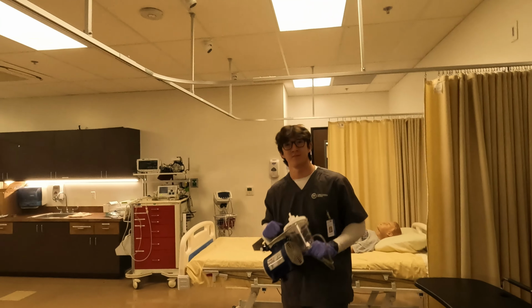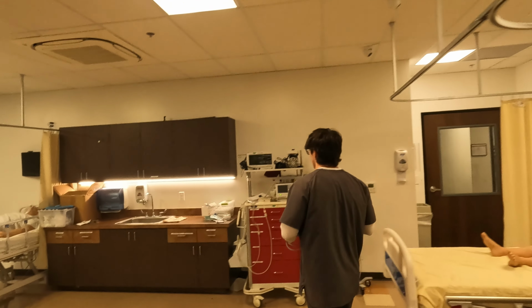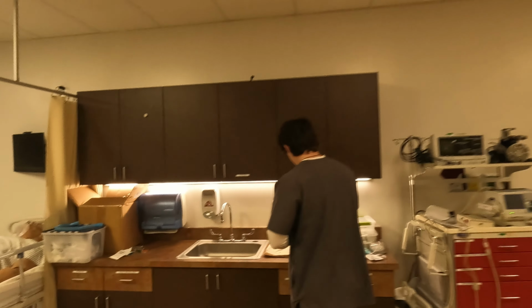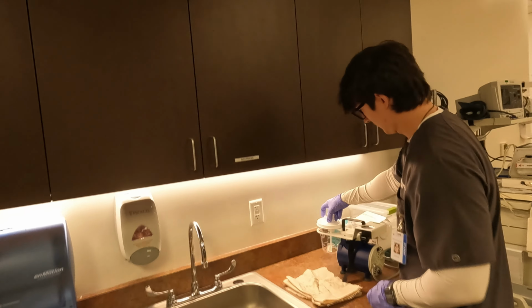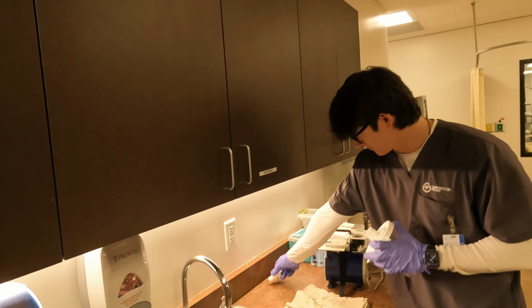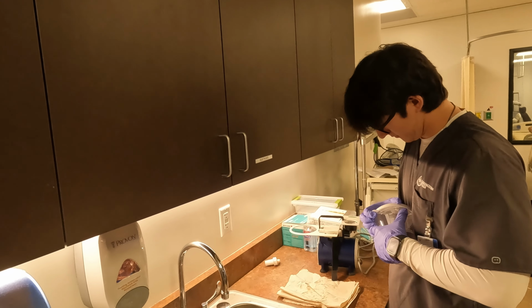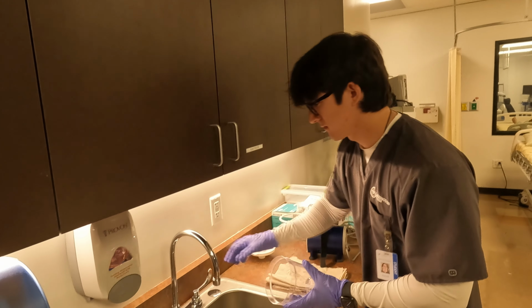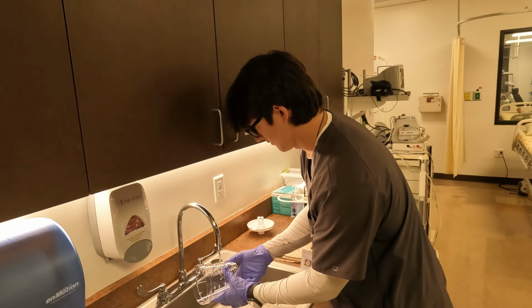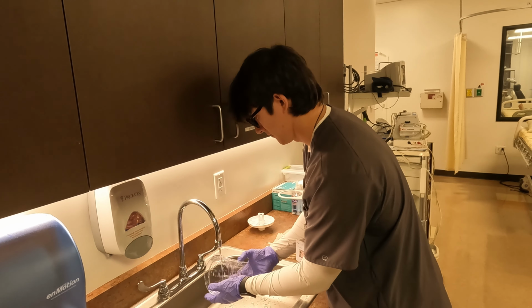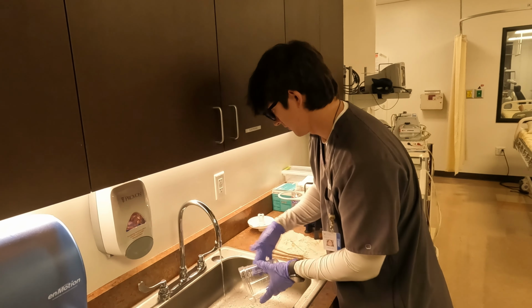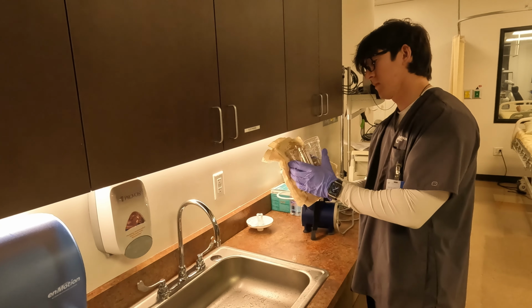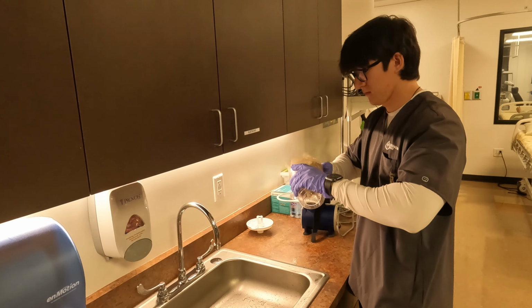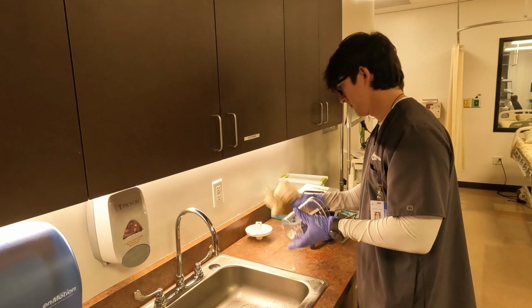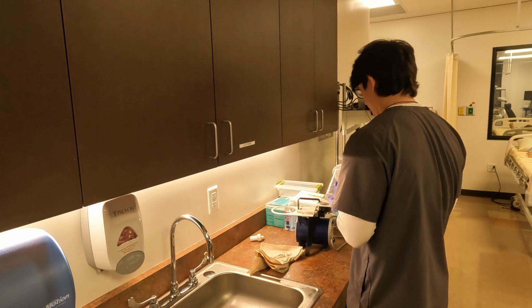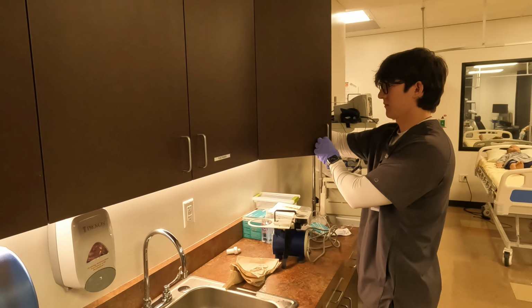Alright, now it's time for the cleaning and maintenance. For the final demonstration, we're going to show you how to clean the canister. Start off by emptying the canister and rinsing. Then disinfect according to manufacturer guidelines. Replace the hydrophobic filter immediately if wet. Once finished, wipe the exterior with a disinfectant wipe. Once dry, store the device in a dry, cool location. And just like that, you're done.